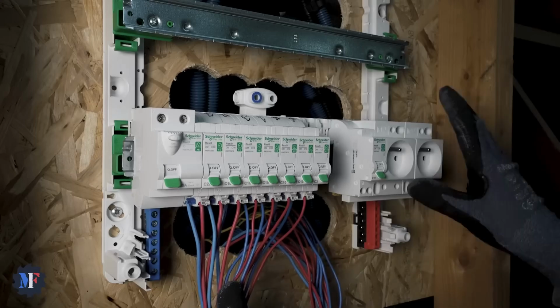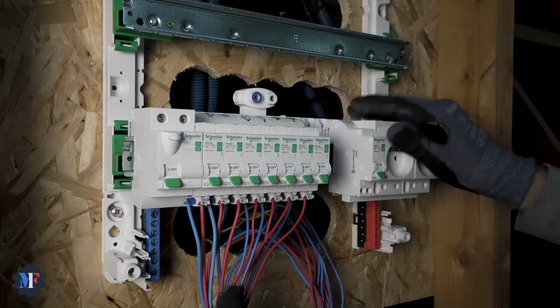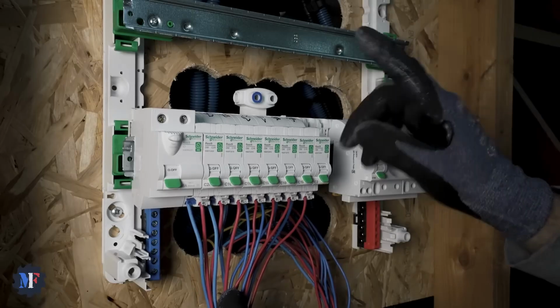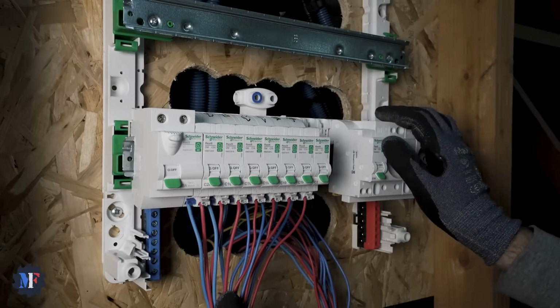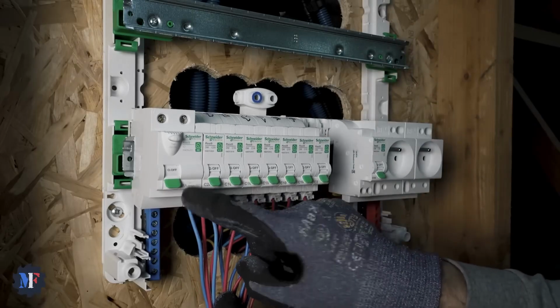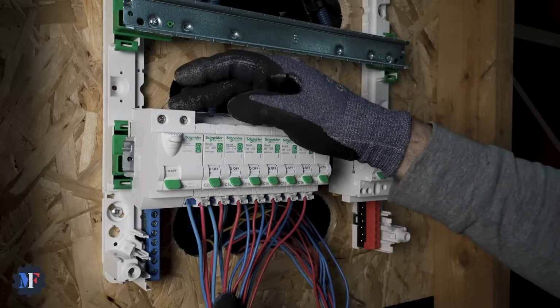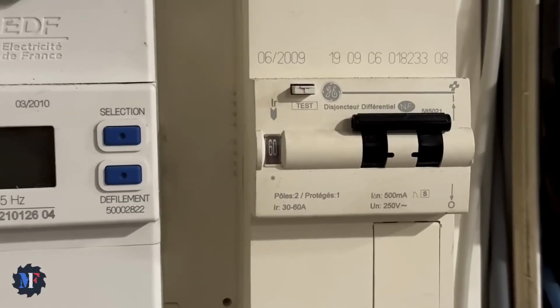No wiring needed, we put it on the distributor and it's powered. It will work once I connect the differential switch. By the way, the differential switch is 63 amps — they're all 63 amps since my main circuit breaker is 60 amps.